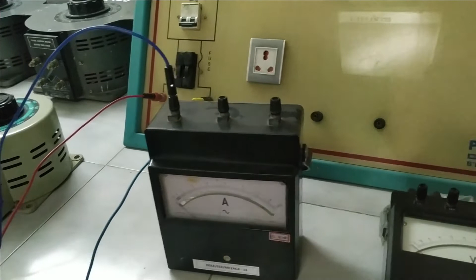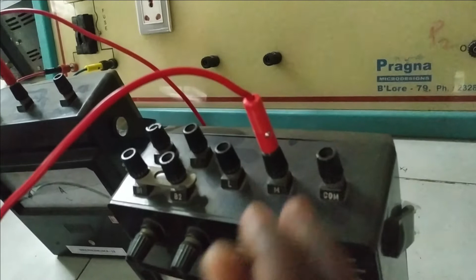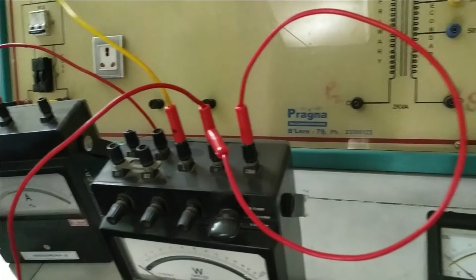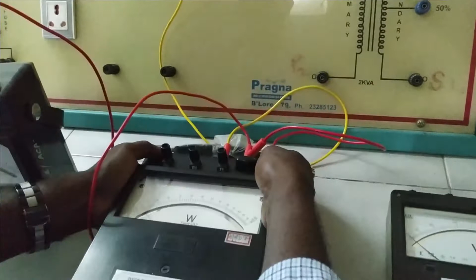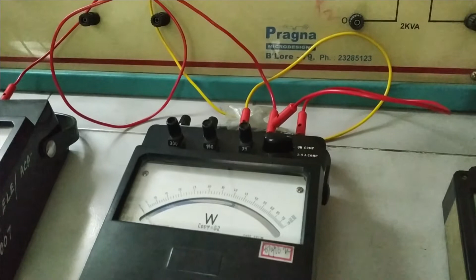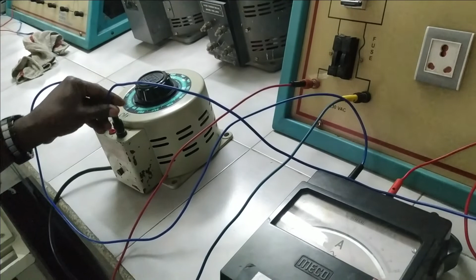Common, then the 2 amperes range is given to the wattmeter terminal M, mains. Then MC of the wattmeter should be shorted. Common and mains terminals of the wattmeter are shorted, and then L should go to the terminal P1. Then one more terminal, P2, should be given back to the auto transformer. Okay. This is how exactly we have done the series connection.